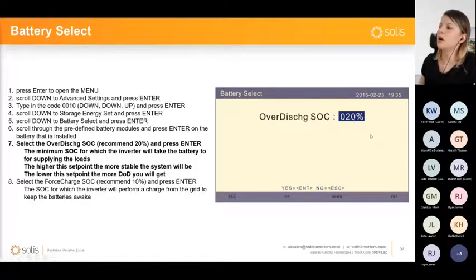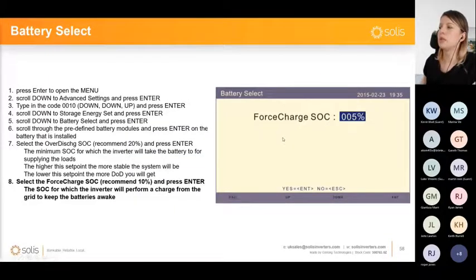So first you are selecting the over discharge SOC, and the next one is going to be the forced charge SOC. This is the level below which the inverter will start charging the battery from the grid. As I mentioned at the beginning of this presentation, the self-use mode normally comes with charge from grid disabled, because not in all countries are customers allowed to charge the batteries from the grid. In some countries it's even illegal, and because of this regulation we have to set that value to not allow.